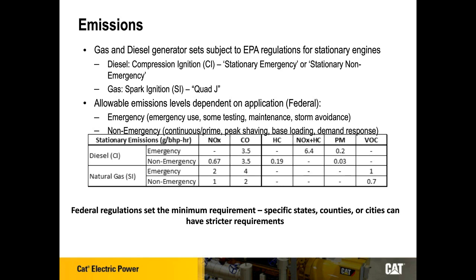As you see on the diesel side, your PM goes from 0.2 to 0.03, for example. And on the natural gas side, for your CO, you go down from 4 allowed at the emergency side to 2 for non-emergency, which is more strict. Again, this is just at the federal level—federal regulations set the minimum requirement, and specific states, counties, and cities can have more strict requirements. We'll get into that a little further.